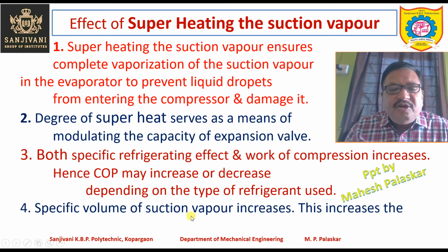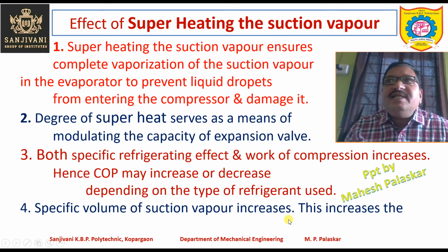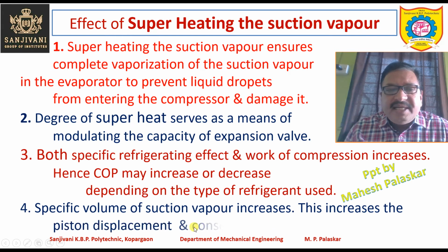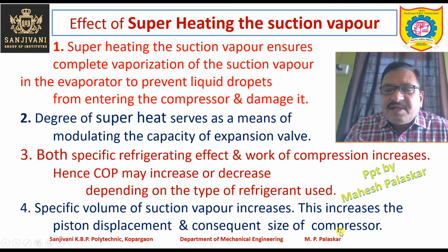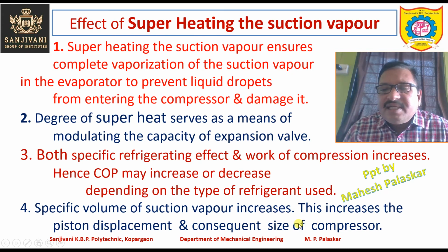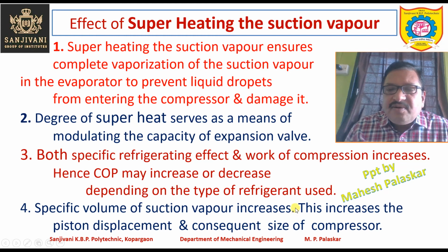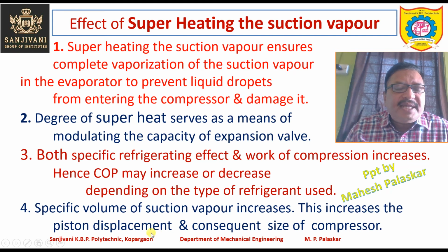So the specific volume of the suction vapor also increases due to superheating, and that will increase the piston displacement and consequent size of the compressor. So the size of the compressor required is also increased due to superheating. So we must go for superheating, but slight superheating is recommended.